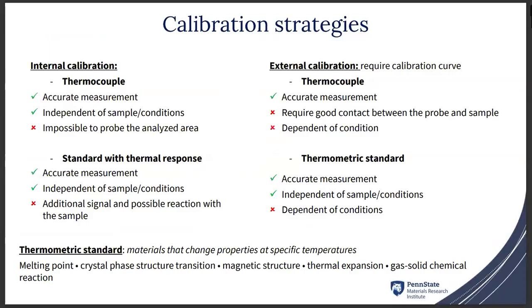So in order to correct that, there is a calibration strategy we can implement, and there are two different types of calibration. The first one is internal calibration, the second one is external calibration. What I mean by internal calibration is we record the temperature, we use a process to have the temperature while we are doing the analysis, which gives a more accurate measurement of the temperature and makes it independent of the sample or the conditions we are using.